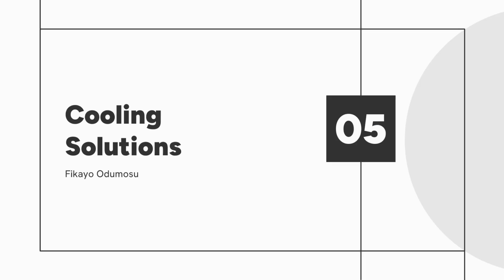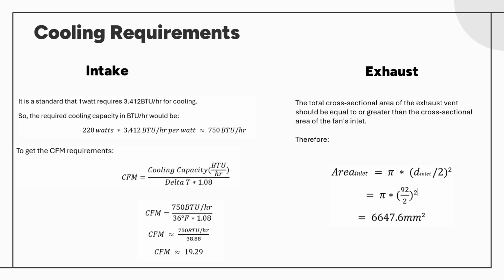The process of defining the cooling for this HPC can be specified. The airflow required to dissipate the heat generated has to be approximated. Both the amount of heat to be dissipated and the density of air must be known. First, we will need to determine the required airflow to adequately cool the components. For this, you can use a rough estimate from the specification of our components.